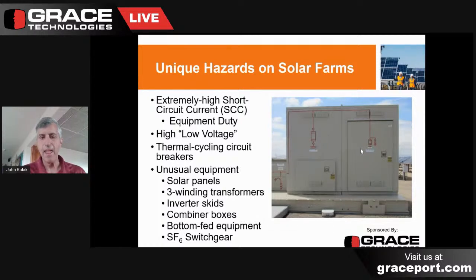Something that's not unique to solar, but wind and solar, is that it's very common to have bottom-fed equipment, meaning you have a circuit breaker mounted in the system, and the source side is actually the bottom side or the low side, the part of the system we normally expect to be switched off when you open the breaker. Well, it's very important on wind and solar farms that we always assume either side of an overcurrent device can be energized, realizing that very, very often the system is bottom fed, which is a non-standard way of looking at how these systems are mounted. Nothing illegal about it. It's just that workers have been electrocuted when they open up a system and even do a voltage check on the wrong side of the equipment and realize that it's energized.